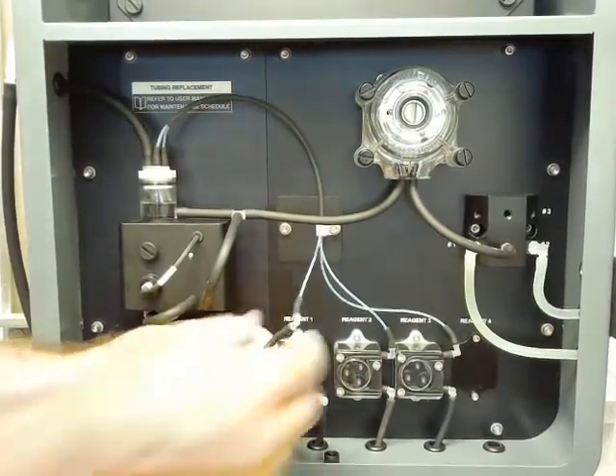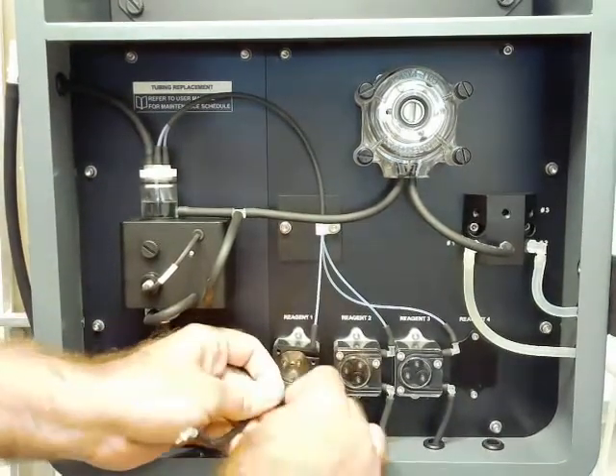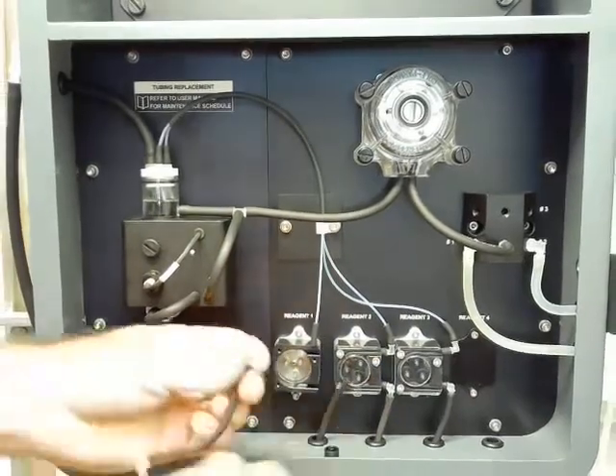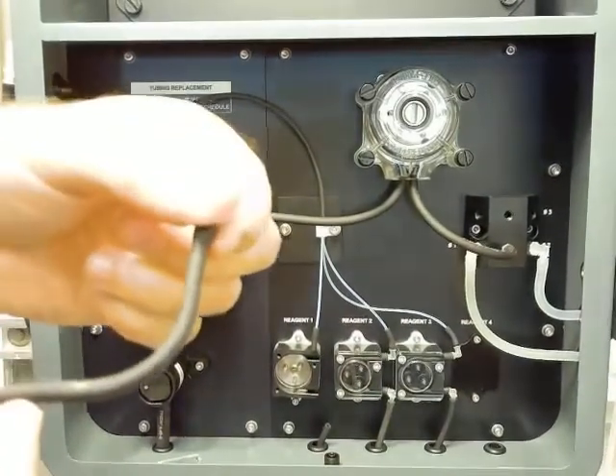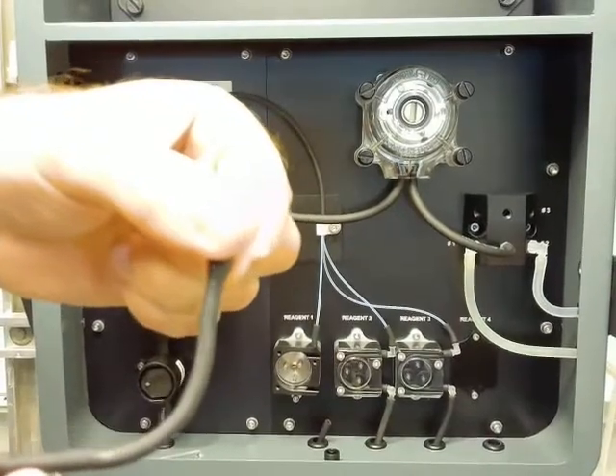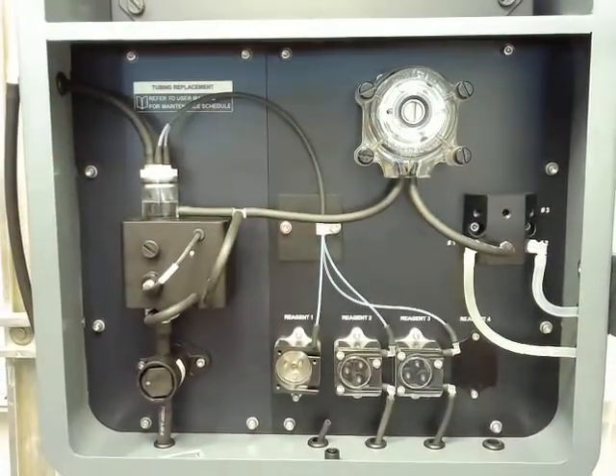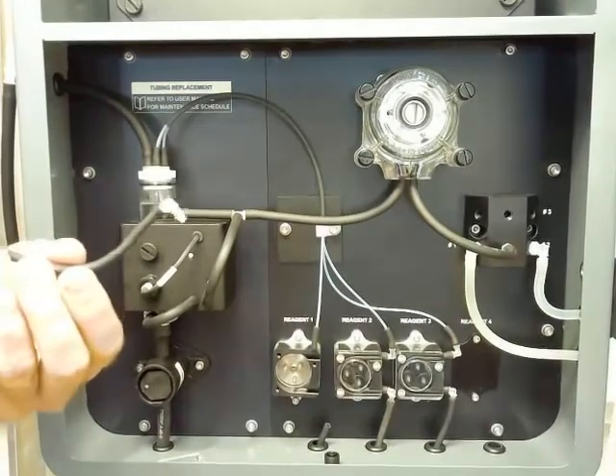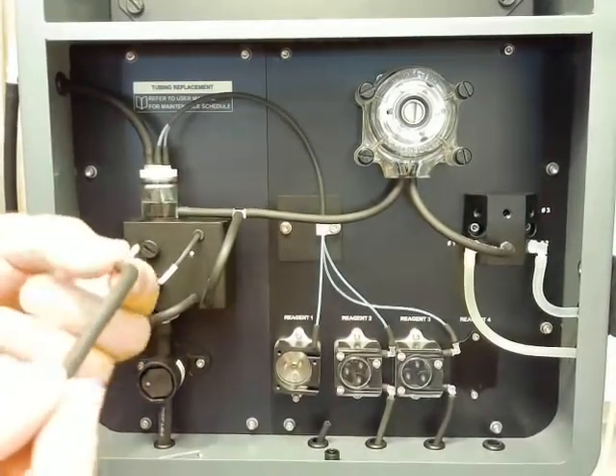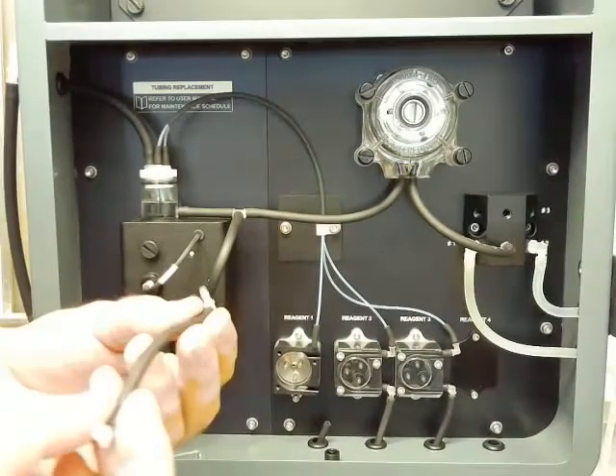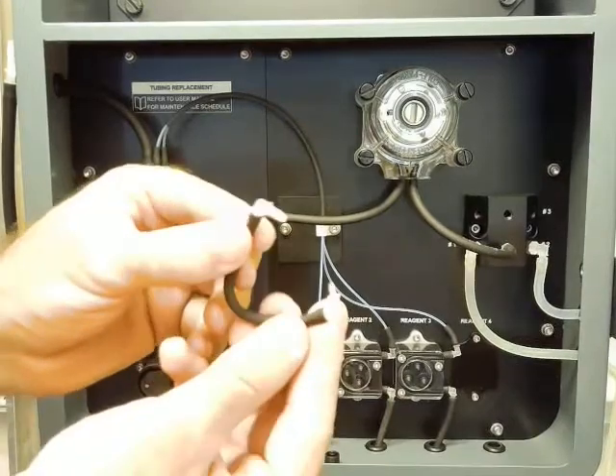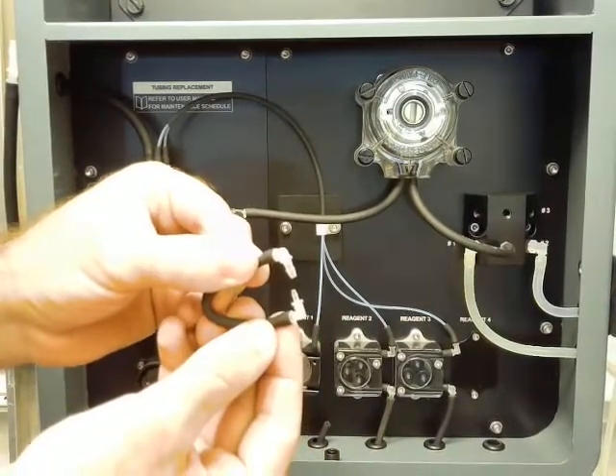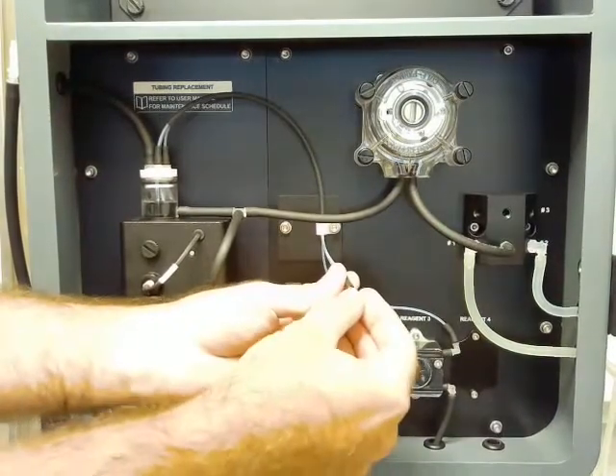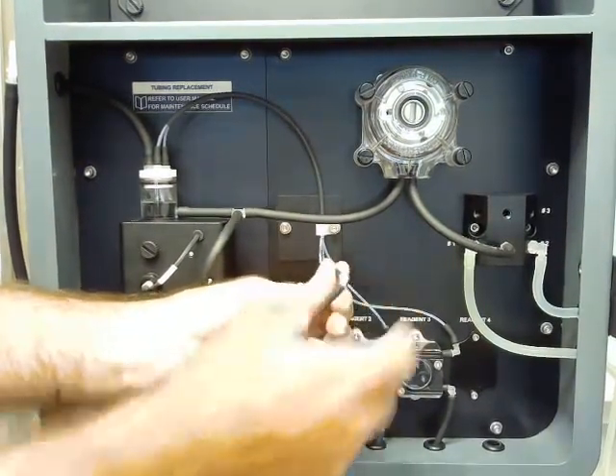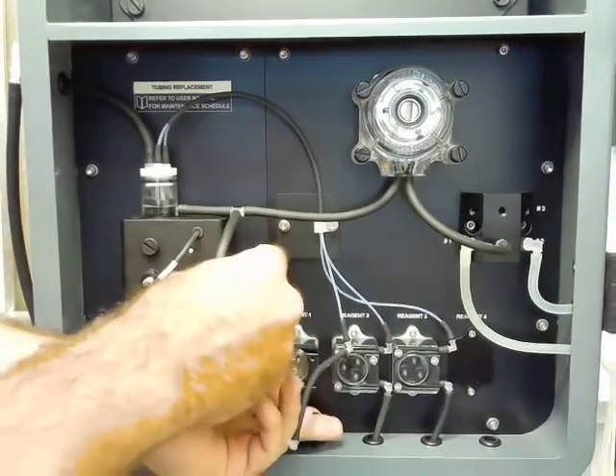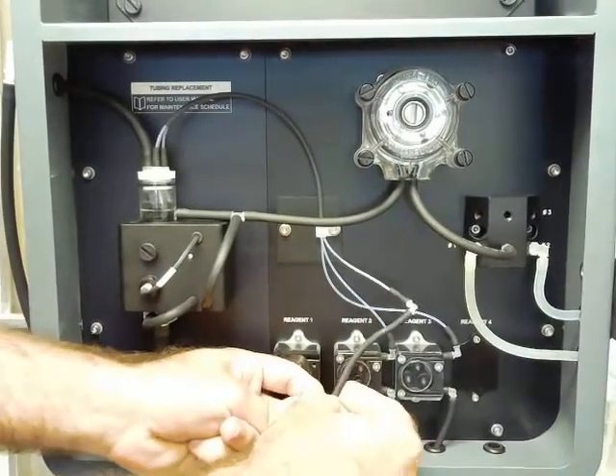And once we have this tubing out, we can disconnect both ends. And then obviously, take a quick look at this again. See, this one's starting to get a little flattened out. Again, that's totally normal. We grab the new tubing, which should be already cut to the right length, and also has new fittings on both ends from the kit. Each end is a different size barb fitting. The smaller one goes up to the top for the tube that leads to the flow cell, and then the slightly larger one goes to the straw at the bottom to the reagent bottle.